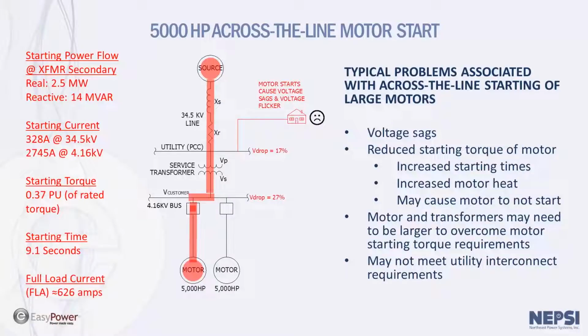In this case, the flow of reactive power from the source to the motor results in a voltage drop of 17% at the point of common coupling, or the 34.5 kV bus feeding this facility. And the secondary was at 27%. So typically, electric utilities will limit the voltage sag at the point of common coupling to about 4%. In this case, the 17% exceeded the utility requirements, and this customer was forced to look for other mitigation options.